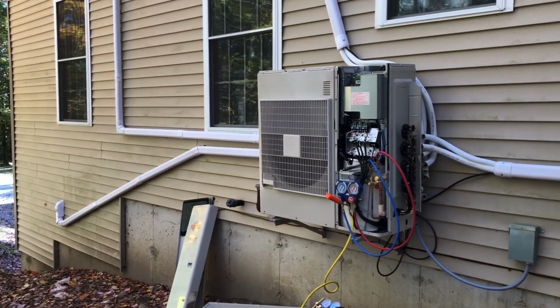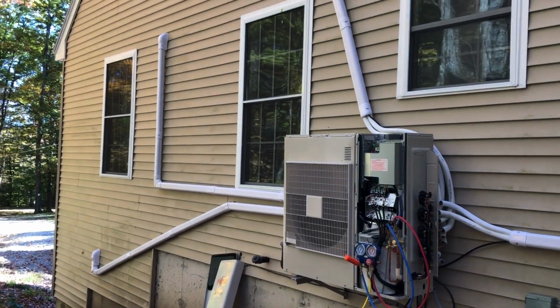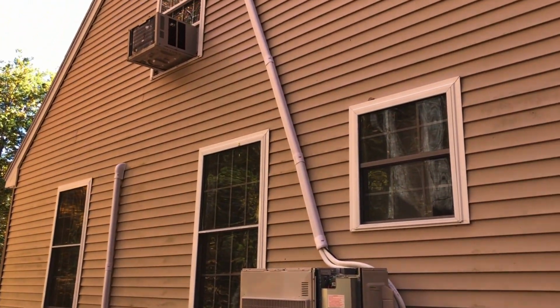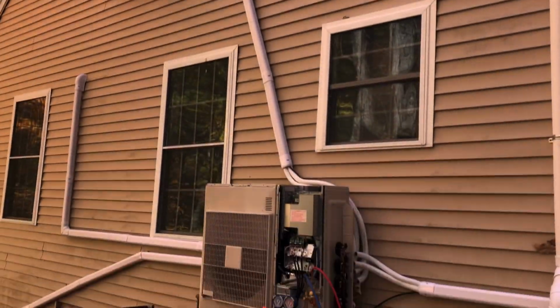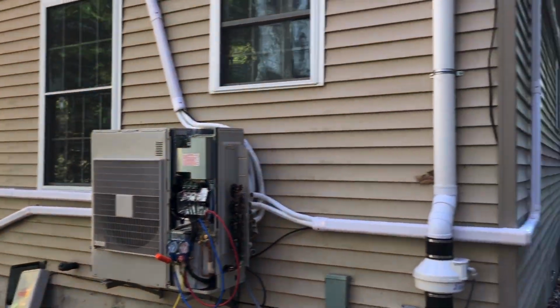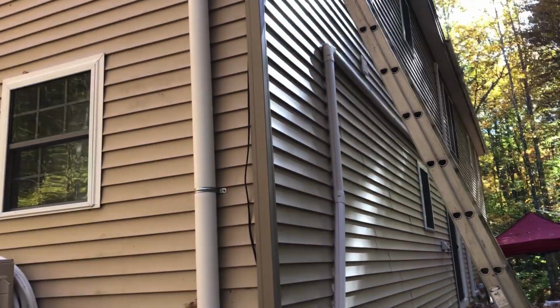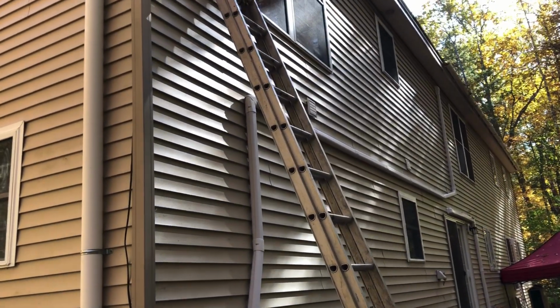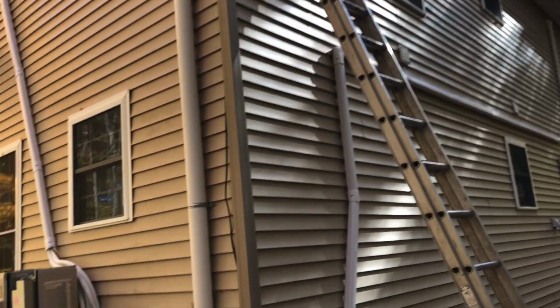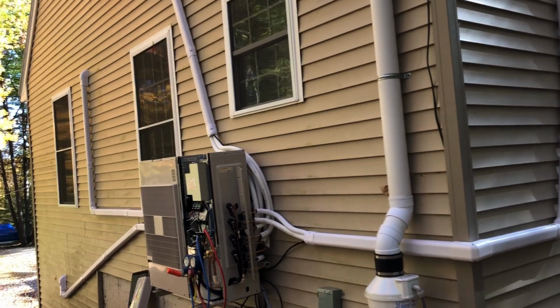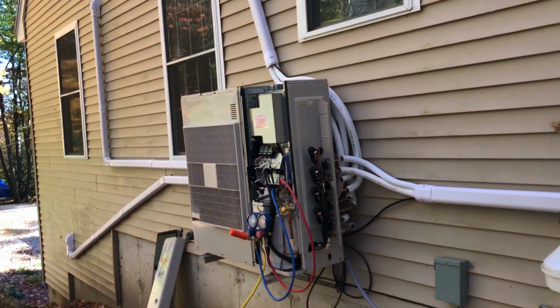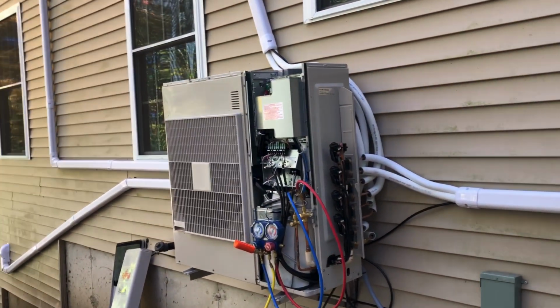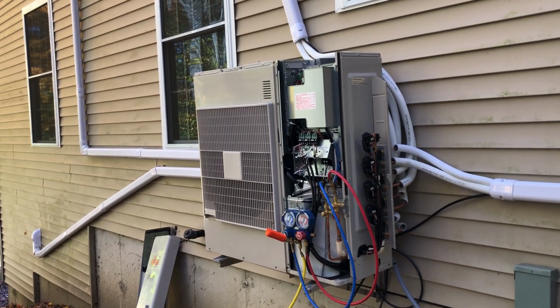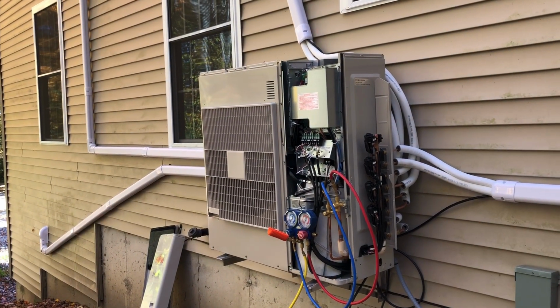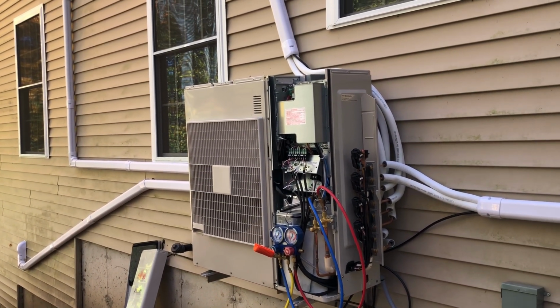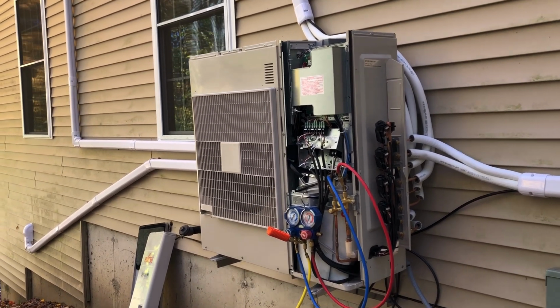Okay, so it's the next day now. Worked all night last night, got all my line sets up and installed. I had a lot of run - about 125 feet. If you have a long amount of run, make sure you read your owner's manual, the installation manual, very closely, because on most units, if you go over 50 feet of line set, you will have to add refrigerant.